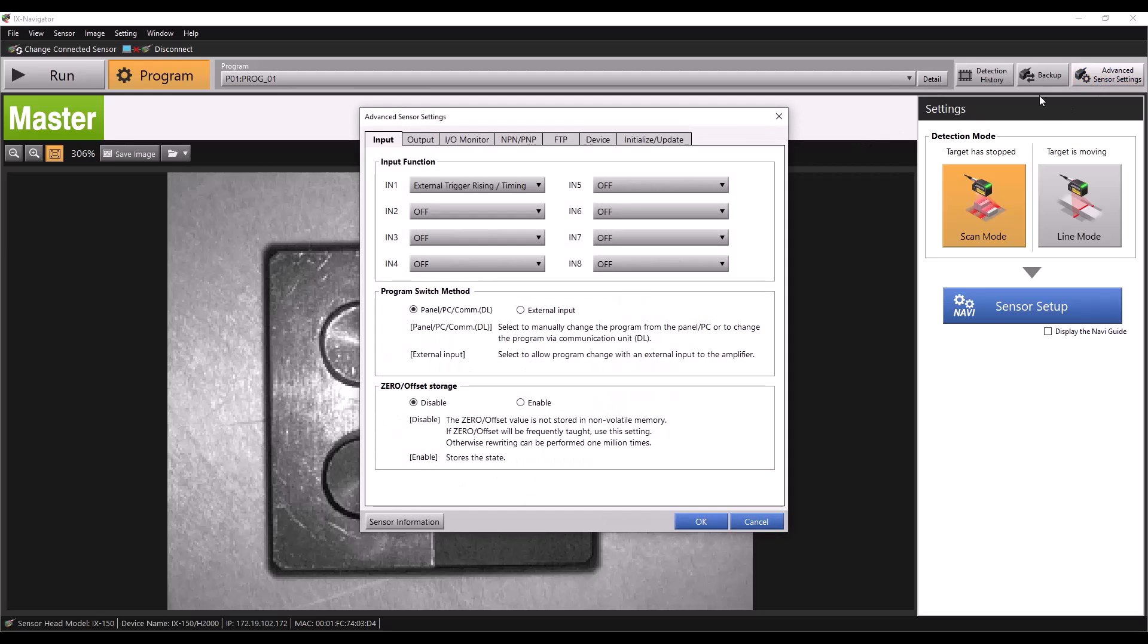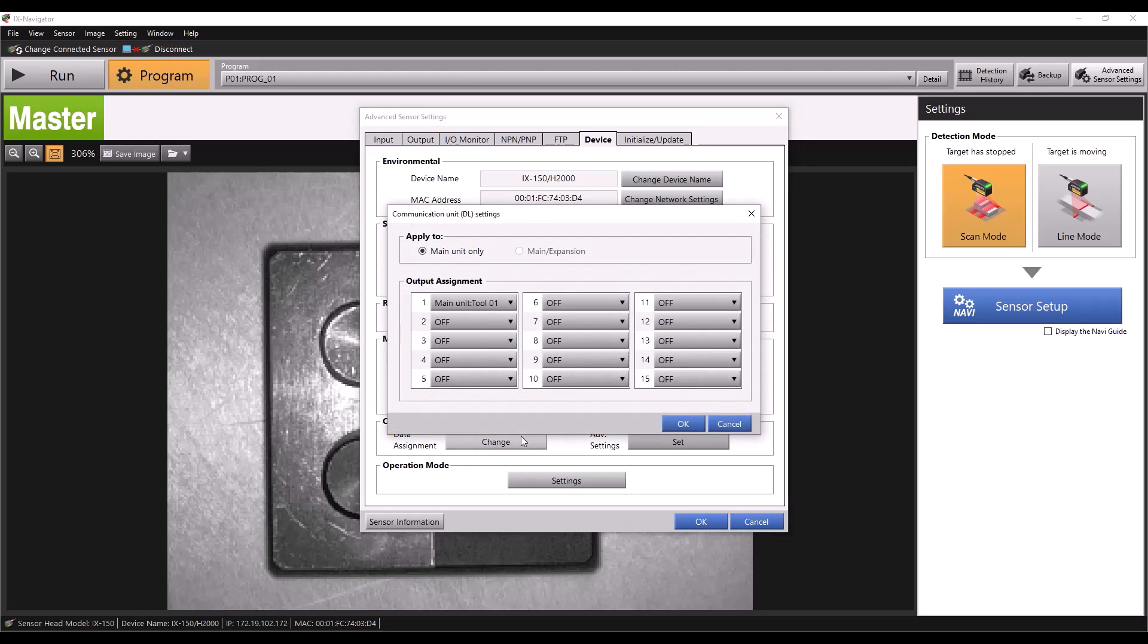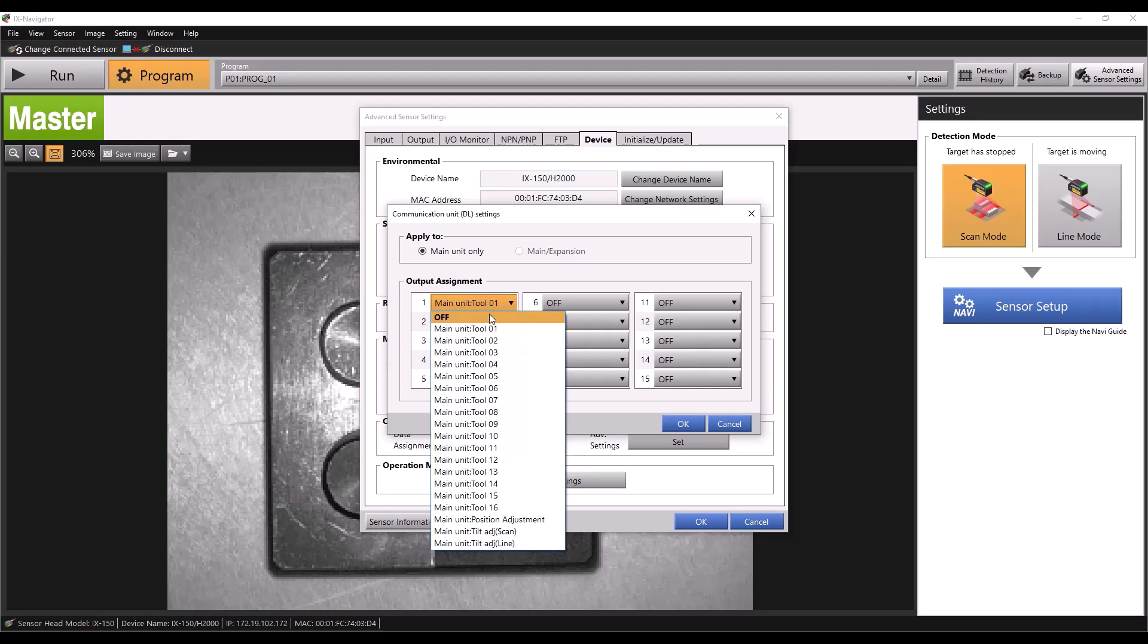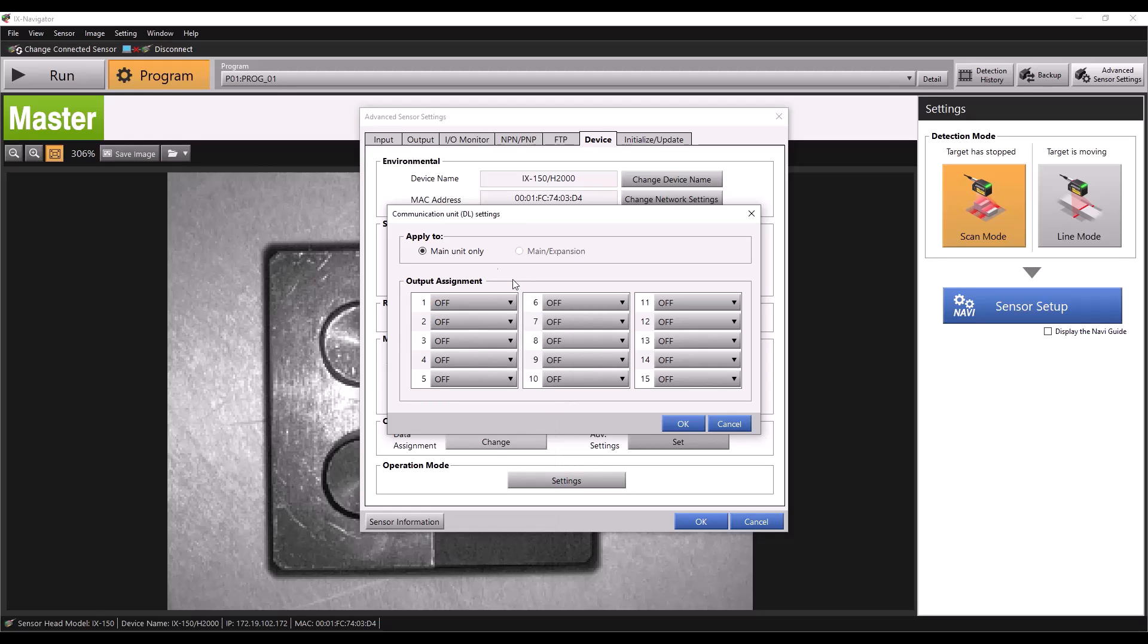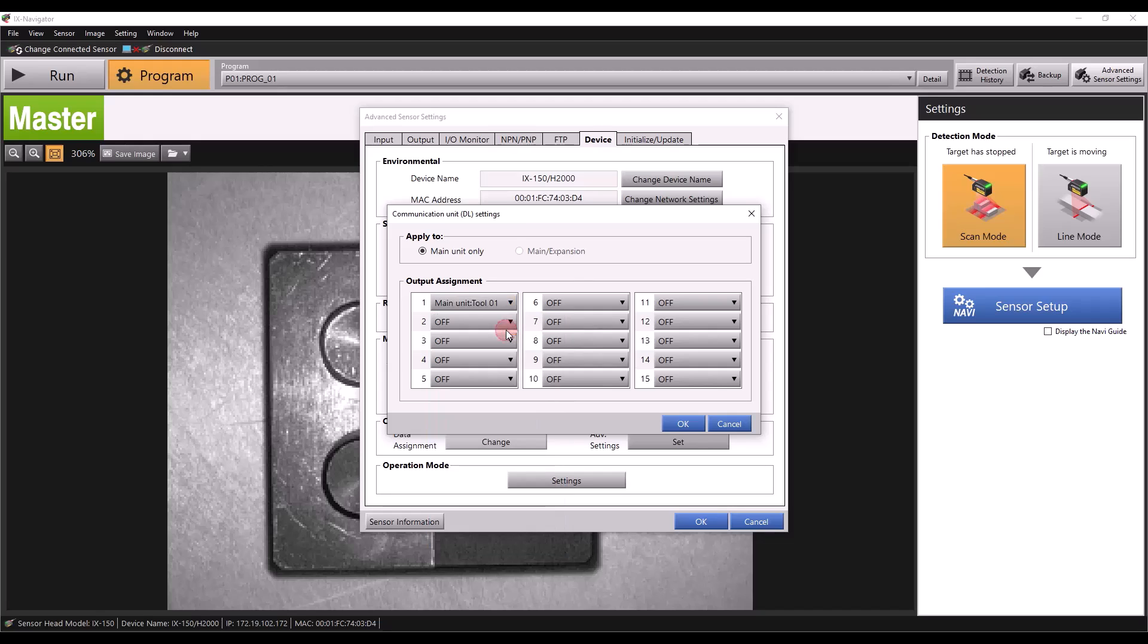so we'll click advanced settings and then the device tab. Then we'll go down to our communication unit DL settings. Click change next to data assignment and you'll see another output assignment window opens. These 15 outputs will correspond to the bits labeled measurement value 1 through 15 in the PLC. I'll set output 1 to tool 1 so that the bit measurement value 1 in the PLC will now display the measured value of tool 1.